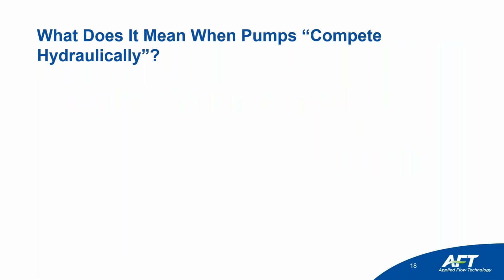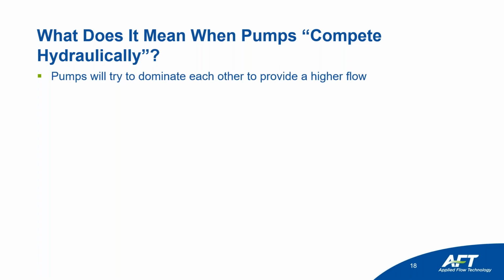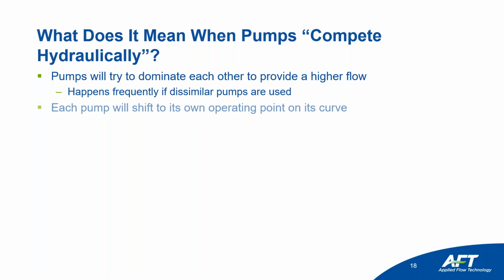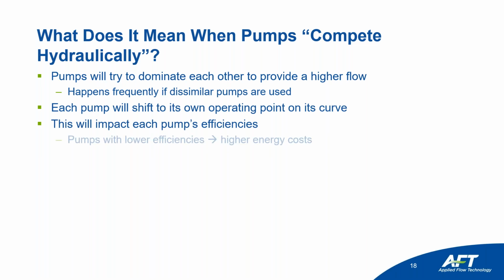Okay, so now I'm going to shift gears and go into some pump and system curve stuff, okay? And we're going to talk about what it means for pumps to compete hydraulically. Well, as I said before, if you've got pumps in parallel, especially if they're not the same, they're going to try to dominate each other, and one of them is going to end up providing a higher flow. This happens a lot if you do not have the same pumps, or if you have different piping for each of the parallel pumps. Each pump will shift to its own operating point that will impact each pump's individual efficiencies.